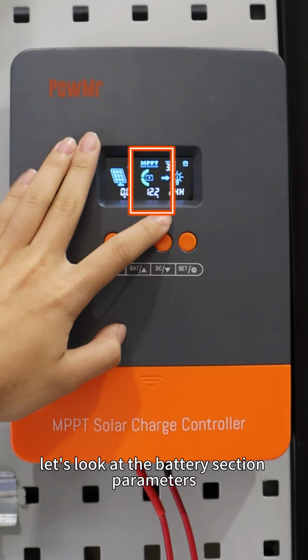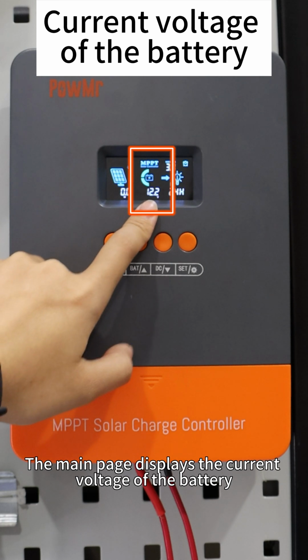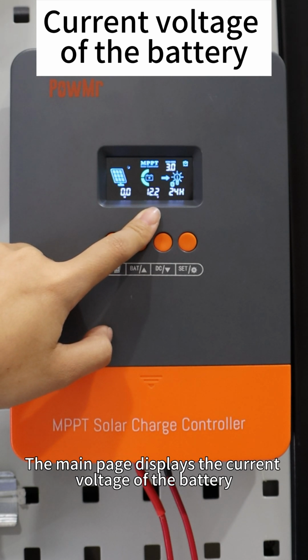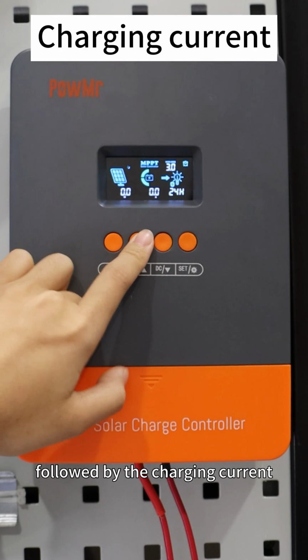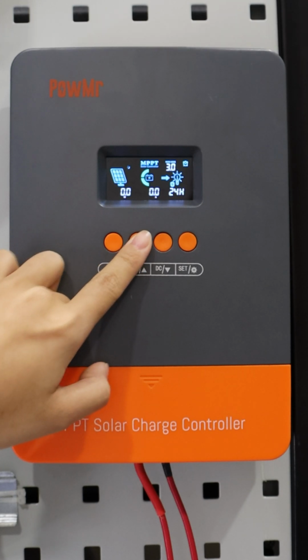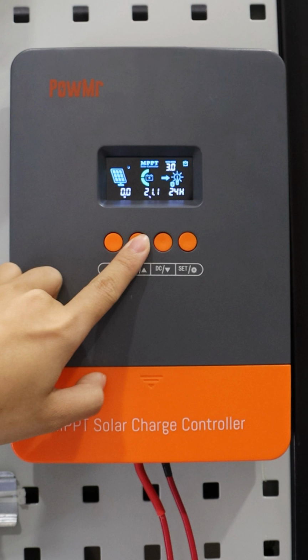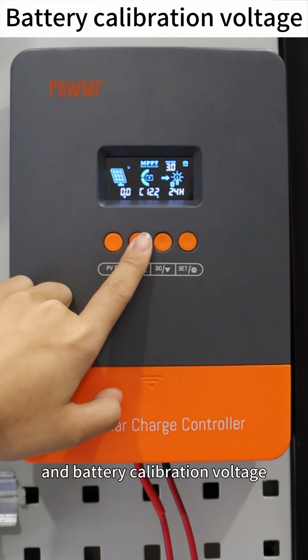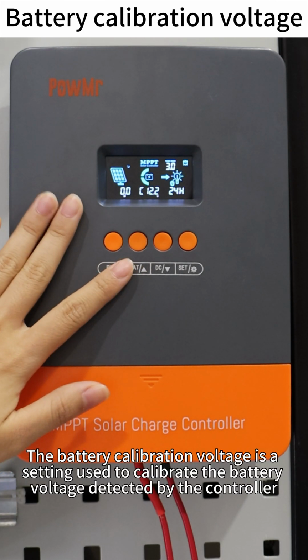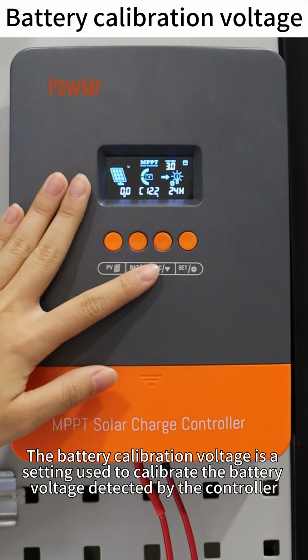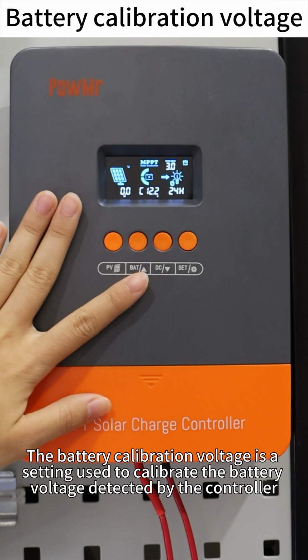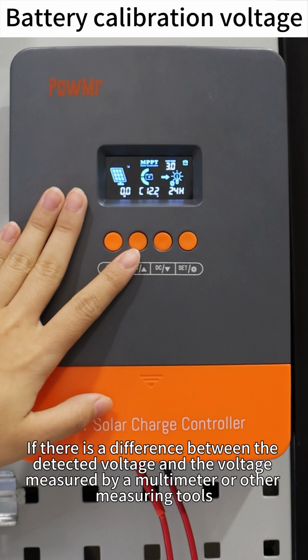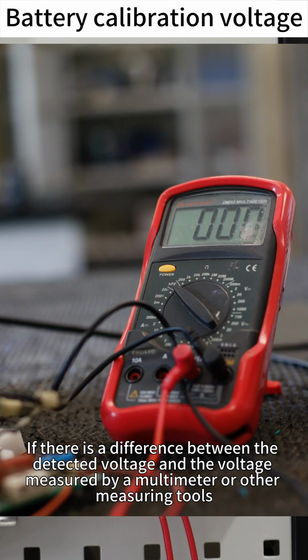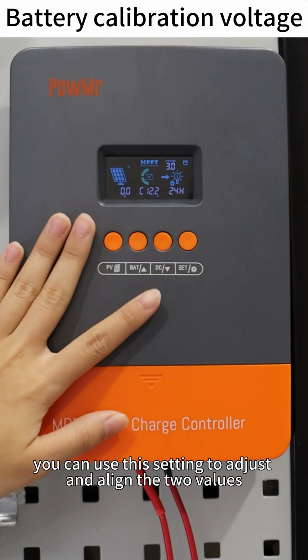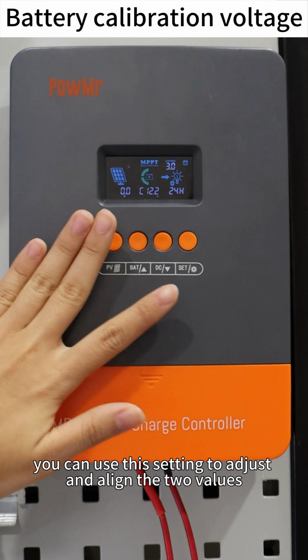Next, let's look at the battery section parameters. The main page displays the current voltage of the battery, followed by the charging current, device temperature, and battery calibration voltage. The battery calibration voltage is a setting used to calibrate the battery voltage detected by the controller. If there is a difference between the detected voltage and the voltage measured by the multimeter or other measuring tools, you can use this setting to adjust and align the two values.